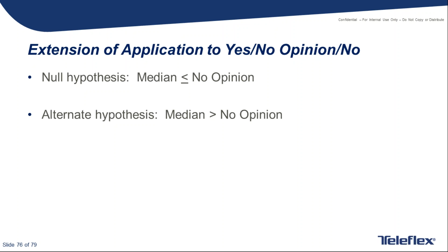If our sample size is only 5, we need all 5 yeses. That's just based on the binomial distribution, so it's pretty simple. And I'm going to have to close there, call it a presentation. The outline becomes a summary slide. We covered risk management and statistics as they apply to sample size determination and testing, design verification, and customer evaluations. And we now have a few minutes for questions.